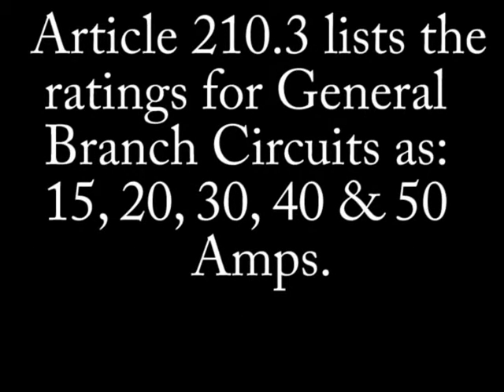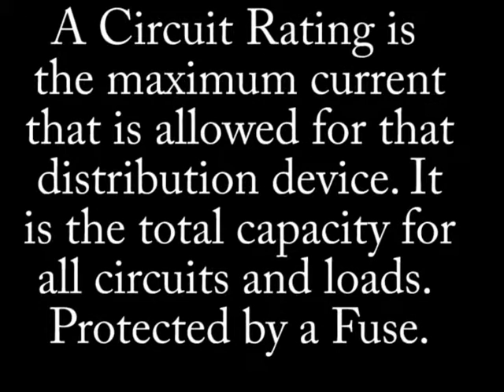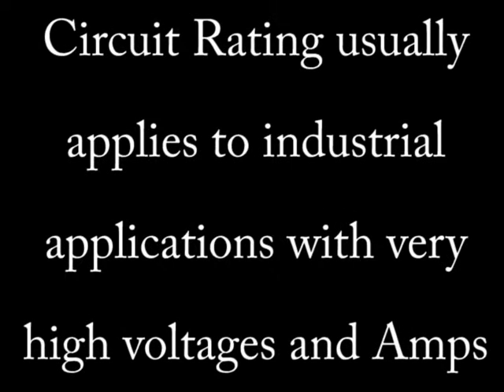Let's get started. Article 210.3 identifies the rating for general branch circuits as being 15, 20, 30, 40, and 50 amps. Amperages of 60 amps or greater will determine the circuit rating. Make a note of this fact. A circuit breaker or overcurrent device is not the same as a circuit rating. In some cases the main service panel can act as a circuit rating, but typically the term is used in industrial applications for very high voltages and amperages.